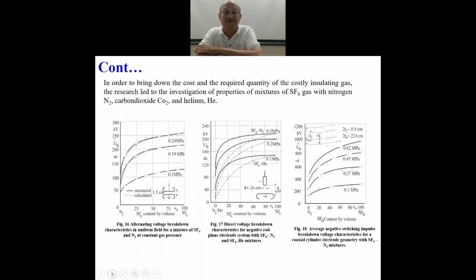So a prime aim of all the engineers is to bring down the cost of the equipment and yet produce high quality equipment. So it was thought to try mixtures of SF6 gas with other gases which have suitable properties. For example, a mixture of SF6 gas with nitrogen. You know that nitrogen is an inert gas. Mixtures of SF6 gas with CO2, carbon dioxide, and helium were all studied, and later it has found wide scale application and brought down the demand for SF6 gas to a great extent. It has brought down the cost of the equipment also.